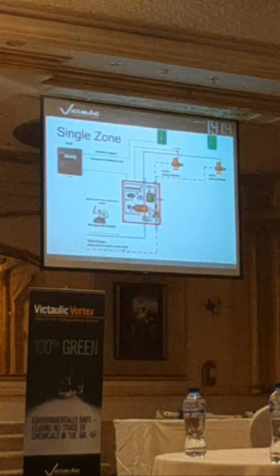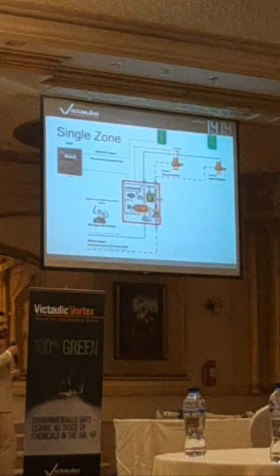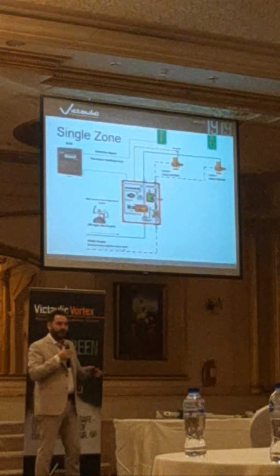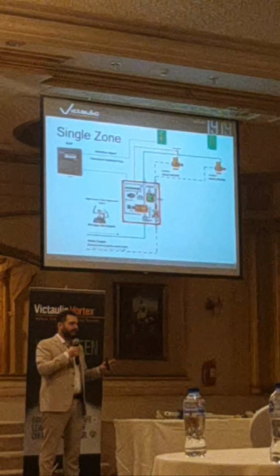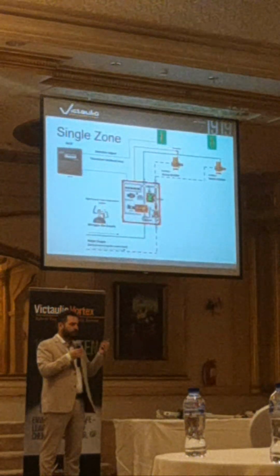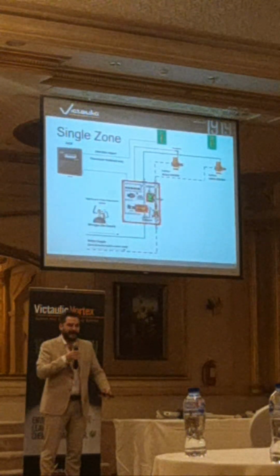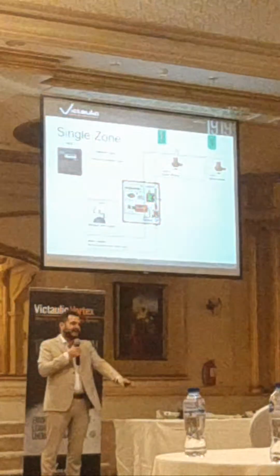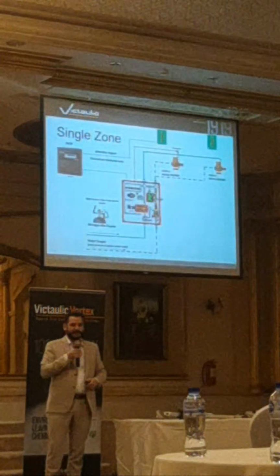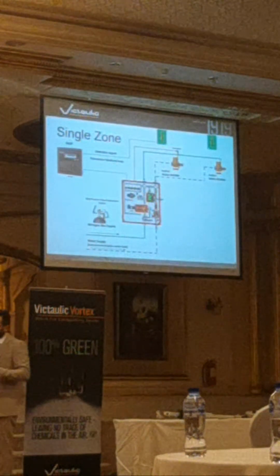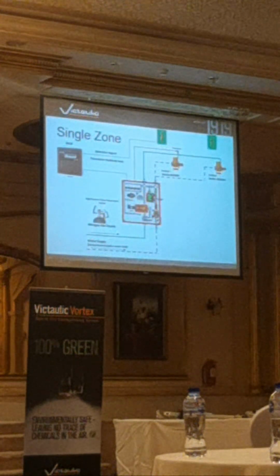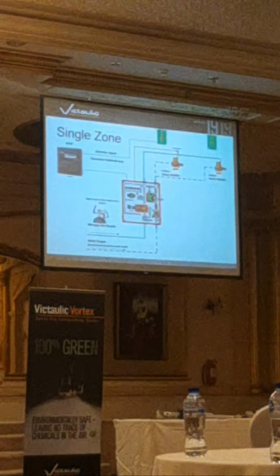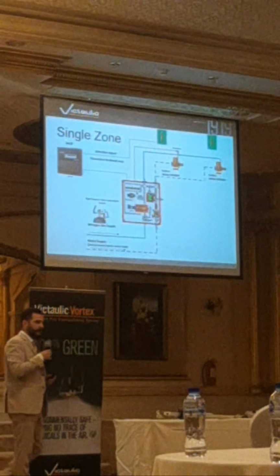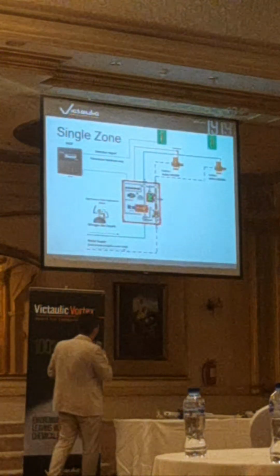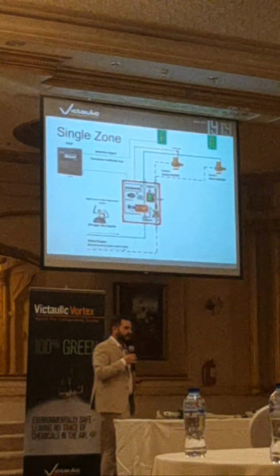At the end of the discharge, the pressure of nitrogen is not sufficient to break down the water, so we close the ball valve of the water first. Again, same principle. We don't want to have water dripping out of those nozzles because there can be sensitive equipment below those nozzles or emitters. And then the rest of the nitrogen will still go out. So that valve will be completely open at the end of your discharge. All right? So that's a little bit how it works. Now, yes?